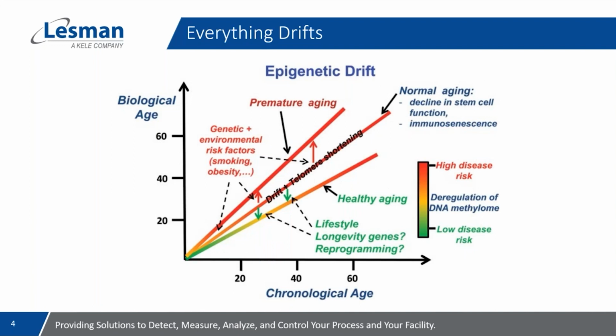The starting point is that drift and aging impacts everything, no matter what. It's not just potential variability between any two sensor elements or people. There can be various influences that impact the rate of the drift, faster or slower. Things like temperature swings, humidity swings, cross-interfering gases, gas exposure itself, contaminants, or even physical interference of the gas reaching the detector. You can design in things to measure the impact of most of these influences, but there will always be some confounding thing that no one anticipated or that you can't automatically detect or measure. And as long as that potential gap exists, nobody's going to sign up for your risk.